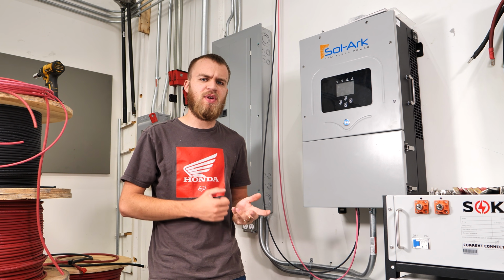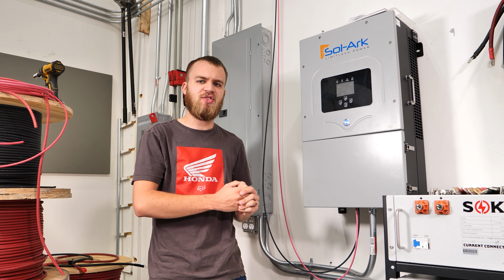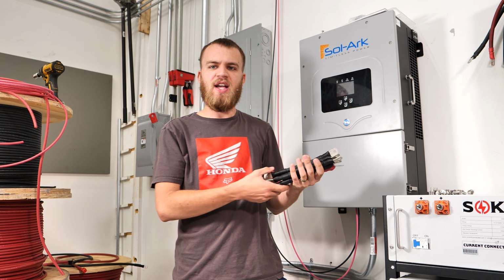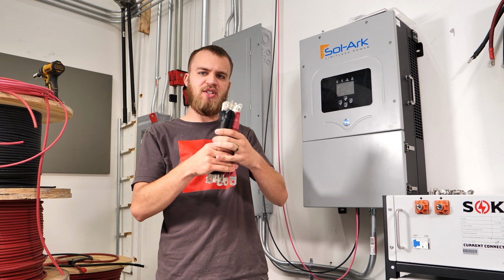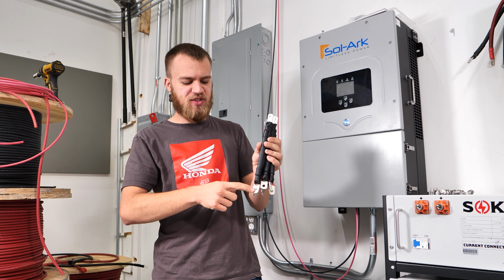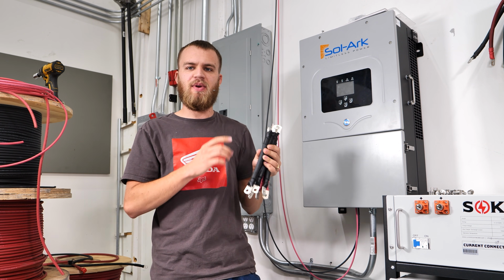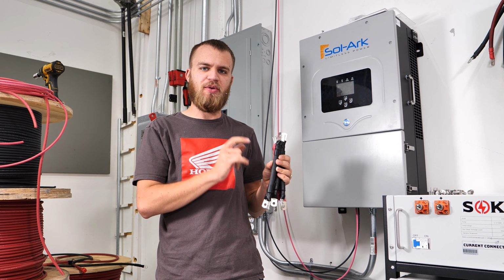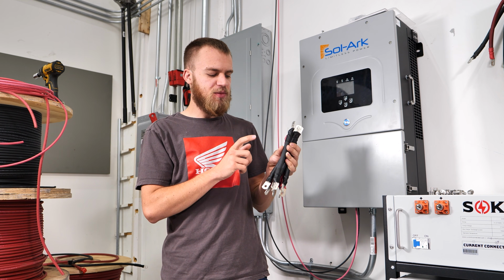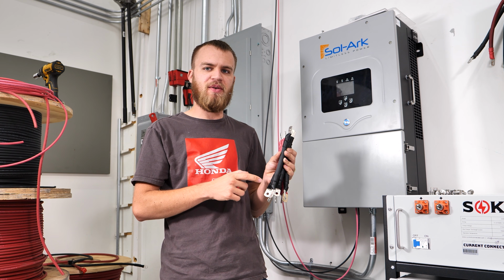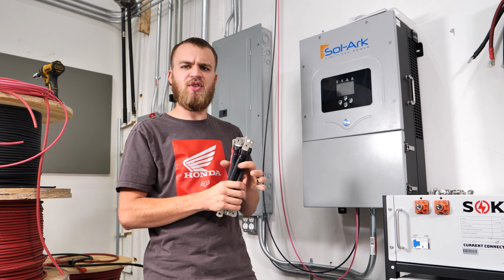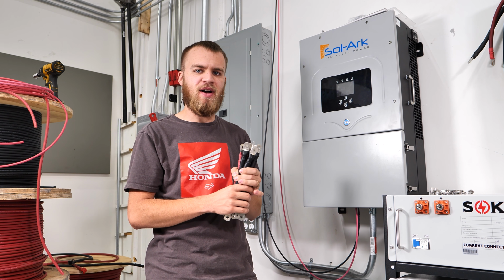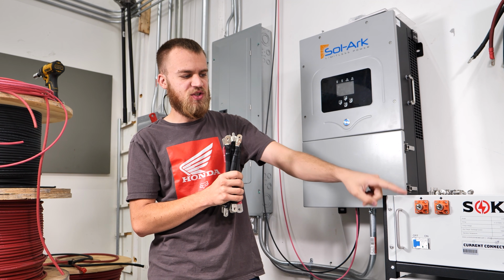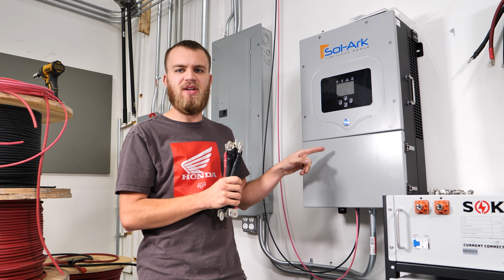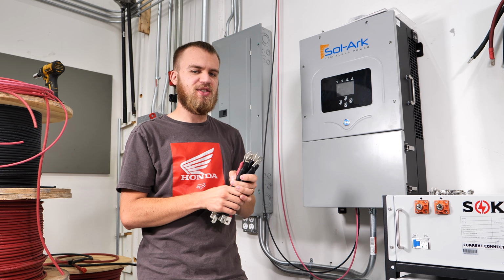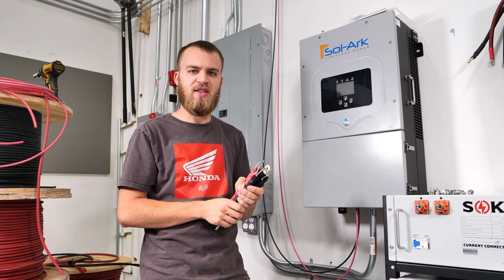Now, while we did get a 2-gauge wire as our minimum, it is also okay to go over that. So today I already have some 2/0 jumpers ready to go. These are 9 inches from center to center, which is the perfect length. We have these pre-made here at Current Connected. I'll put a link down in the description. So like I said, I'm using 2/0 for my battery-to-battery connections, only because I'm going to be doing multiple demos. 2-gauge would be perfectly fine, and in fact, I'm using 2-gauge wire to go from the rack to the inverter. So just to give you an idea, it's based on the inverter you hook up, not necessarily the batteries.